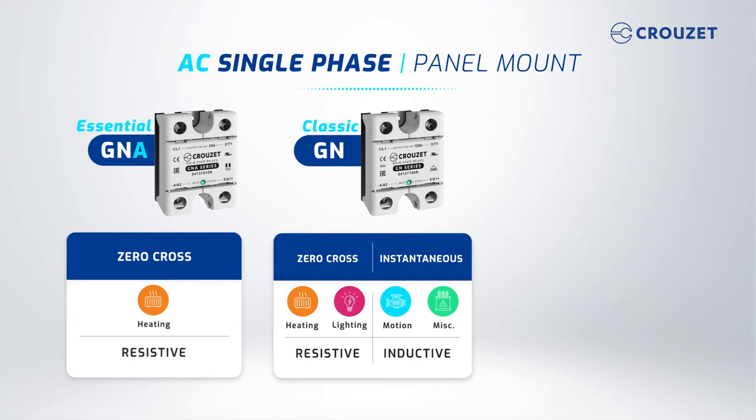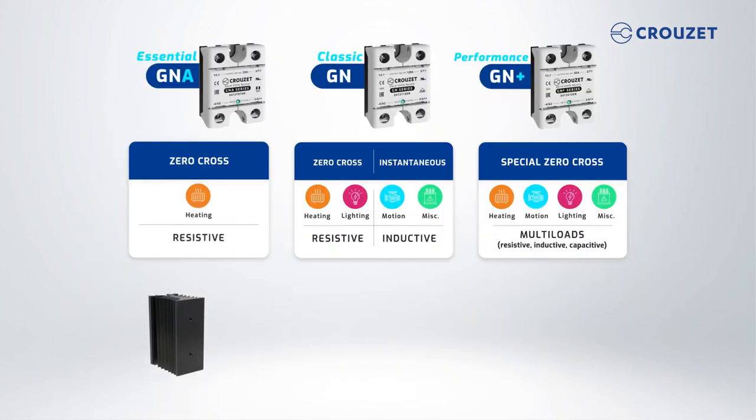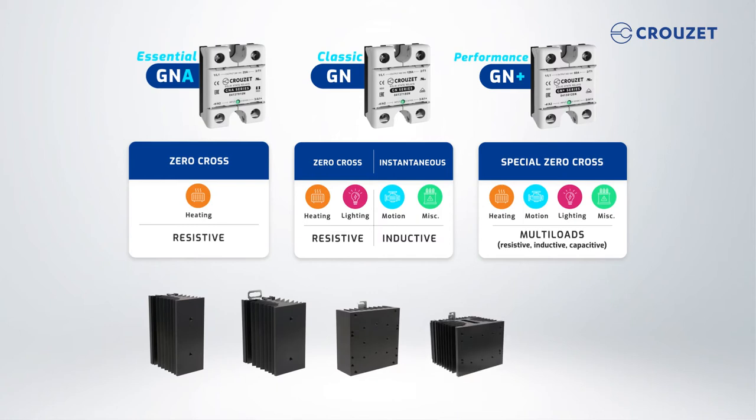You can also select a more robust product with the GN-plus series. This offers higher immunity and overvoltage protection, which can handle any type of load — resistive, inductive, or capacitive. Panel mount SSRs need to be mounted to a heat sink. To achieve the desired current at different temperatures, you can find a list of available heat sinks at crouzet.com.